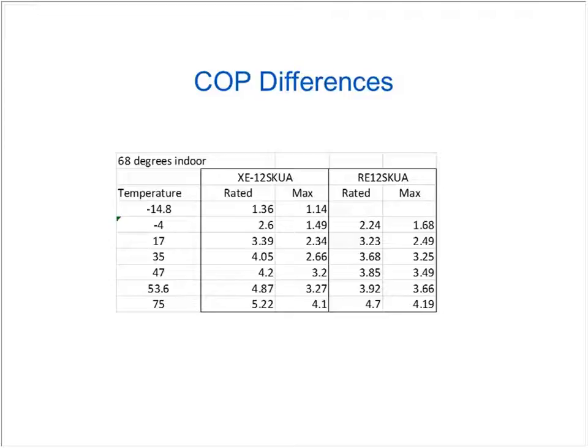So when I say max, that's maximum output. For example, if it was just on high, let's say it's 47 degrees outside and you put the indoor unit on 80 degrees, that's going to speed up that compressor, or try to, but the rated value says it's only going to be at that 4.2, and the rated value is fixed at 47. So in a 68 degree indoor, you can't really tell what the high speed is going to look like from there.